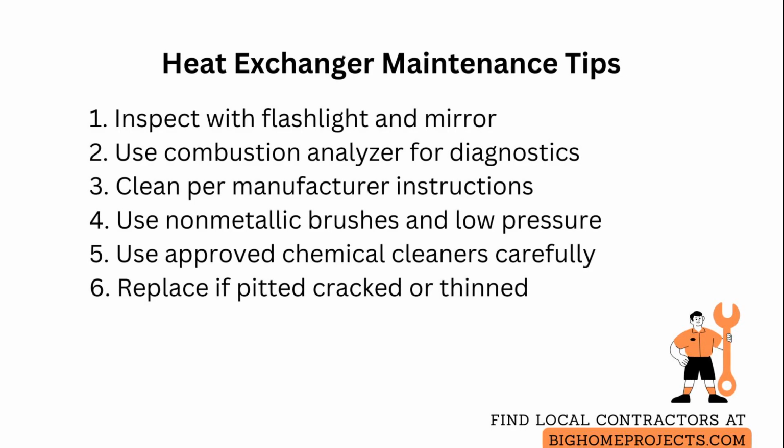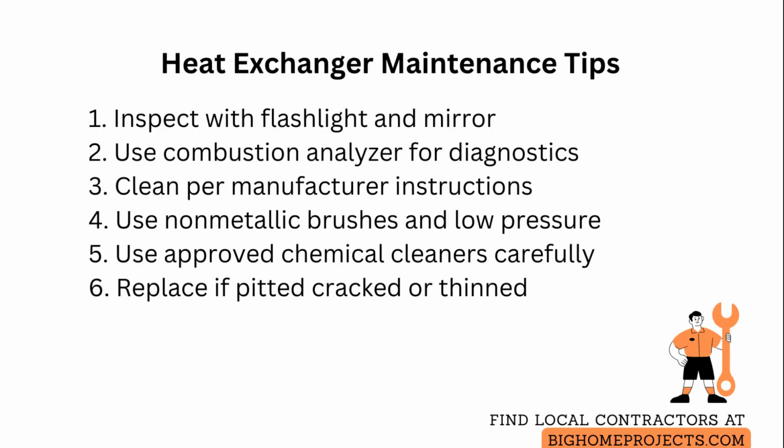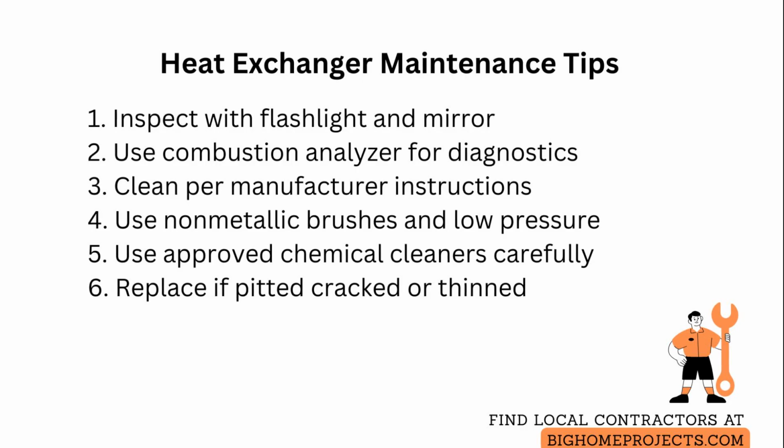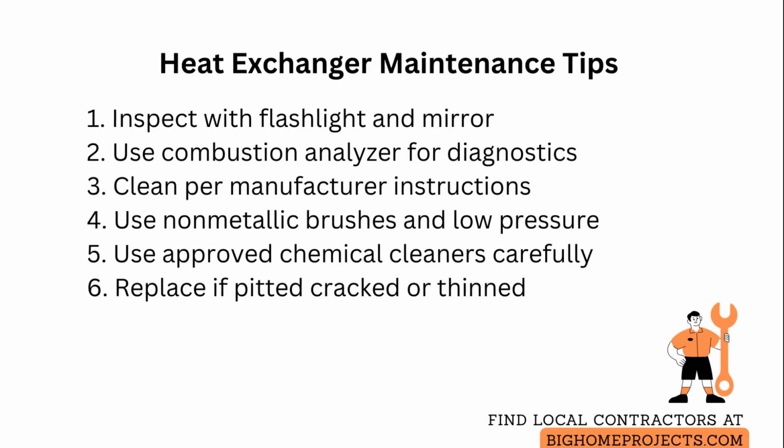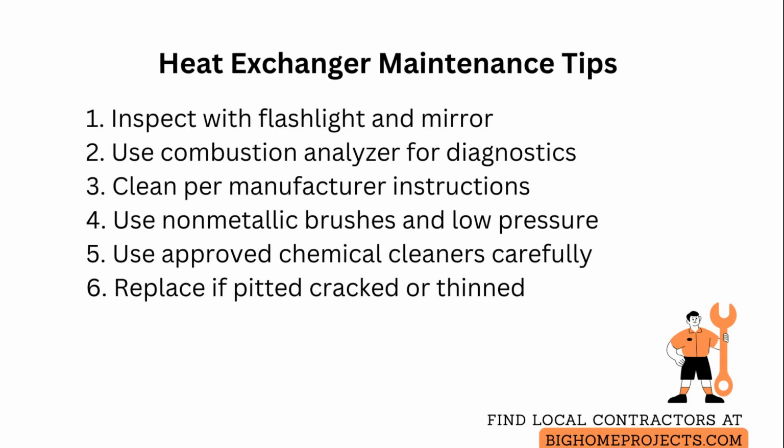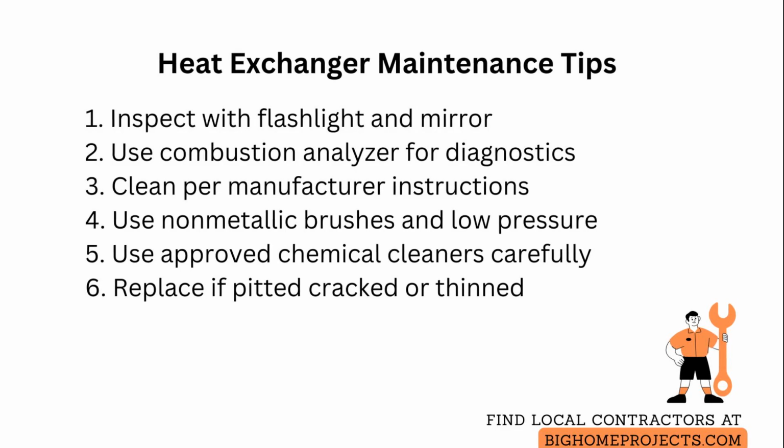To diagnose this at an expert level, start with a visual inspection using a flashlight and mirror for accessible sections, and use a combustion analyzer to check for abnormal stack temperatures and carbon monoxide patterns. For cleaning, follow manufacturer guidance. Use non-metallic brushes, low-pressure compressed air, or approved chemical cleaners, taking care not to damage thin walls or seals, and always decontaminate surfaces if soot is present.